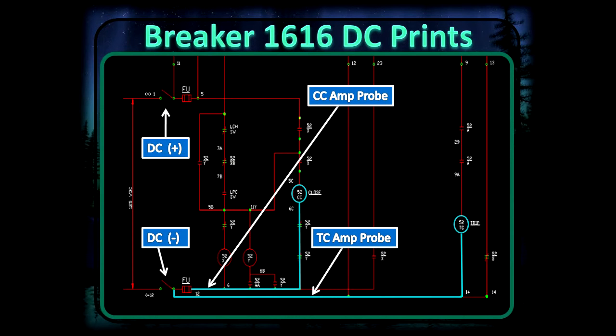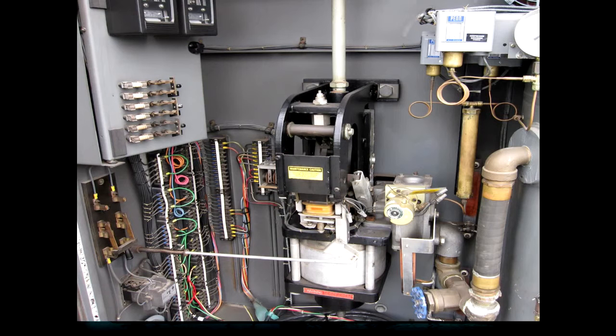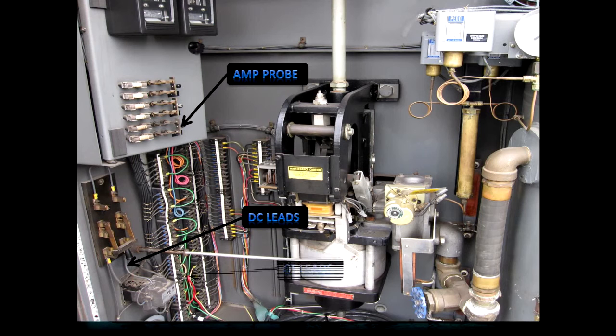So once we go to our prints and we understand that, we'll go to the cabinet of the breaker, and that's what this here is. And using our electrical prints corresponding with the physical layout, we're able to tell where our DC lines are. So this is where we would hook up our DC leads to the test. Our amp probe will be over here because these are the leads going to both the trip coil and the closed coil. And then our CT leads will be connected here.